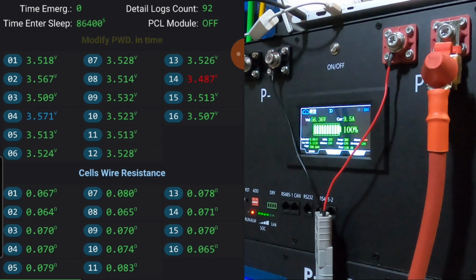But I'm even satisfied with this. If you can basically sit there and have a resting voltage of 55.2, that's where you're going to float at anyway. So if you can float for 2 hours, when you're floating, you're not going to be pushing 9 amps, you're going to be pushing less than 1 amp. So the deviation is going to stay in check. If you can sit there and float for 2 hours at 55.2, you're good. So I consider this, for all intents and purposes, balanced.